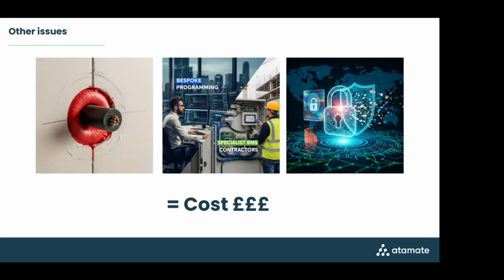Other issues I've already alluded to involve cabling. This picture here is fire stopping. Most of the systems are currently cabled, and because they use bespoke cables, you're pulling cables across a building, and buildings are divided up for fire purposes into different zones. Every time you go through those zones, you need to make sure it's fireproof, so it's quite disruptive pulling cables around, particularly in existing buildings.